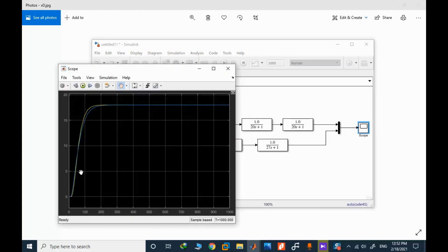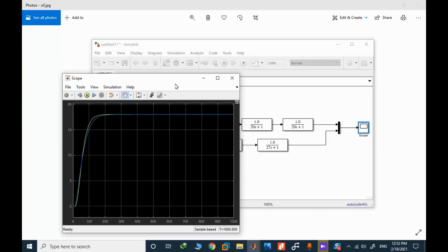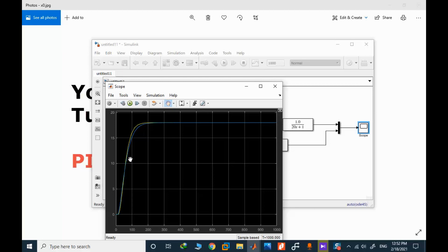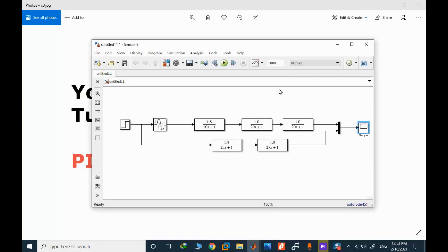You can see that in the simulation the yellow curve is the actual third order process model, while the blue line is the approximated and estimated process model. Their step response perfectly matches, and this ensures us that the calculated PID and PI parameters can be used in the actual DCS platform in order to control any complex temperature or high order process models.